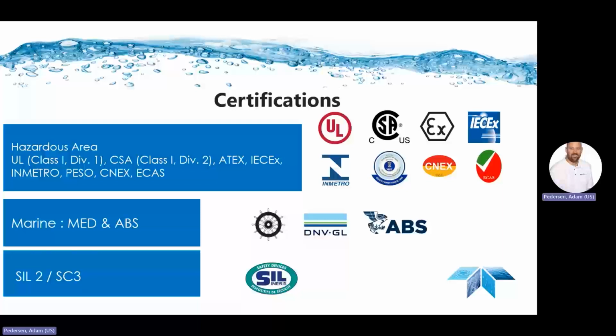The onboard watchdog circuitry continuously monitors the GD10P's electronics and firmware, providing true fail-safe operation. The sensor performance meets or exceeds CSA and ATEX requirements, and the GD10P circuitry has been tested by third party for use in SIL 2 rated systems. So the GD10P Div1 provides all the same benefits as the standard GD10P, but is UL approved Class 1 Div1 rated enclosure with an NPT fitting.